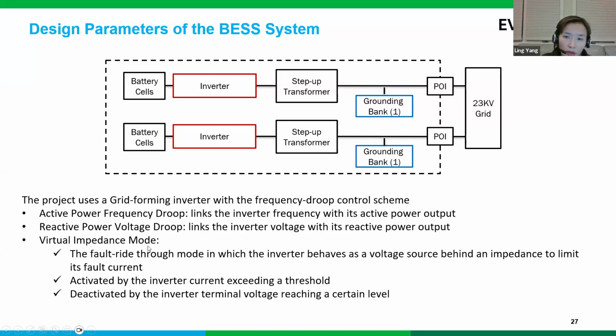The virtual impedance mode is entered once the inverter senses there is a fault in the system. This mode is activated by the inverter currents, and it is deactivated by the terminal voltage, so its activation and deactivation are controlled by different parameters. Some of these settings at the very beginning, the OEM, the manufacturer, was not opening up, and they had default settings. So we worked with the inverter manufacturer quite a lot through the process, and they had to open up the model and some of the control parameters and customize them for our design.